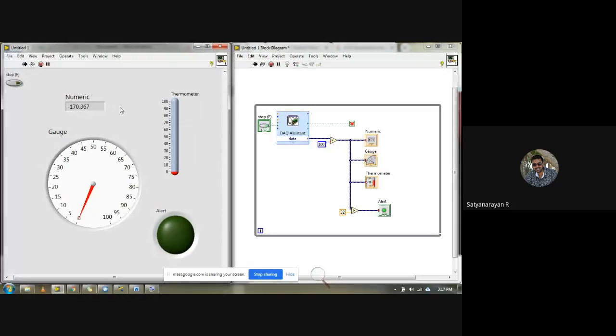But when you connect the previous wire, AI0 minus to AGND, you will get the actual voltage or actual temperature. Now I hold it tightly, and I can see it gradually increasing. And I leave it, and you can see it keeps moving randomly. Why? Because I have not connected a proper negative terminal, meaning the differential end has not been connected to ground properly. Once it is connected, you will ultimately get a proper result.